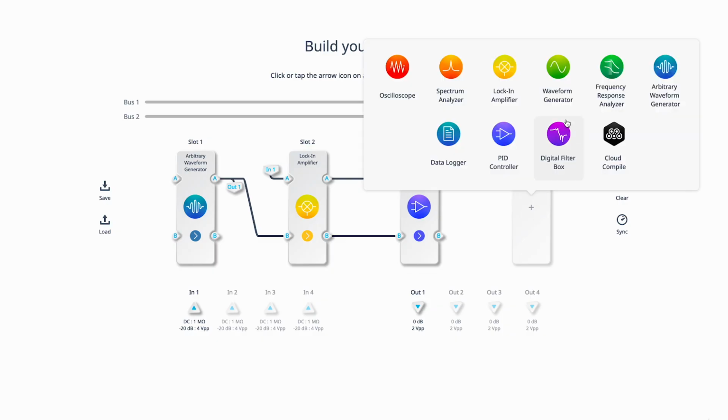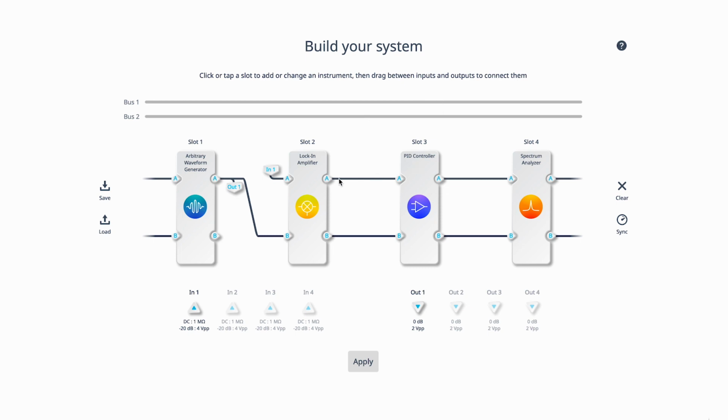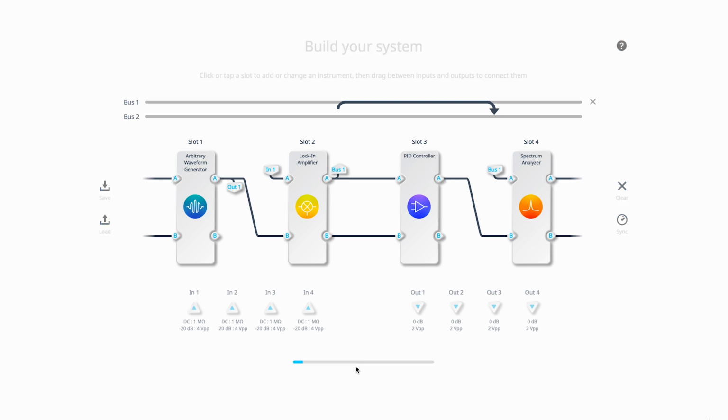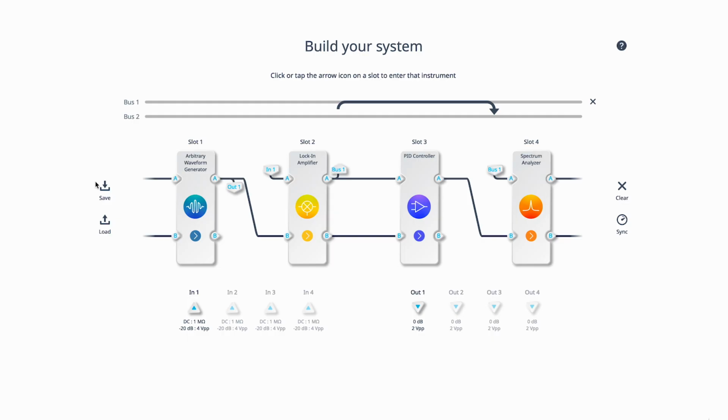By integrating multiple instruments into one hardware device, multi-instrument mode allows you to take up less lab space, increase asset utilization, and reduce cost. You can also build custom test configurations on the device FPGA with low latency, lossless interconnections, which improves synchronization and reduces cabling. With full access to device outputs, inputs, and back panel triggering, it's easy to generate, measure, and process multiple signals simultaneously. You can also hot swap instruments in and out without interrupting those running in the other slots.